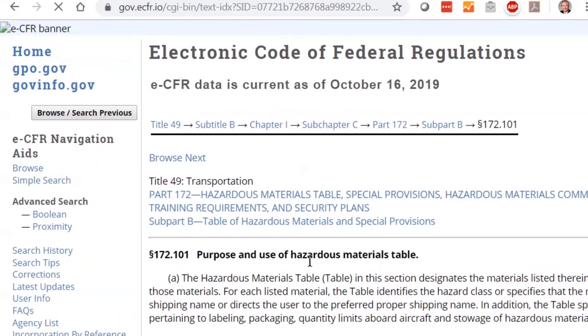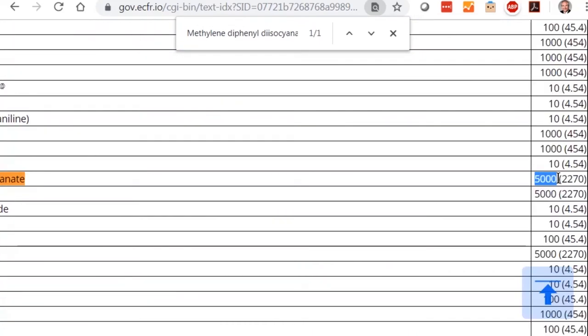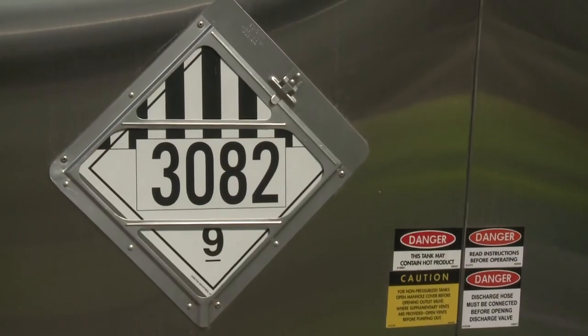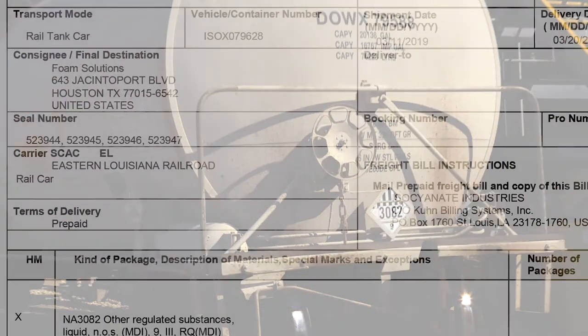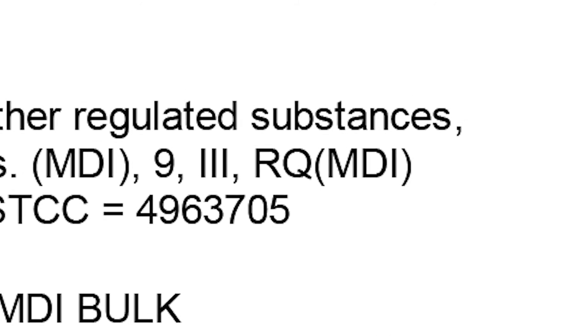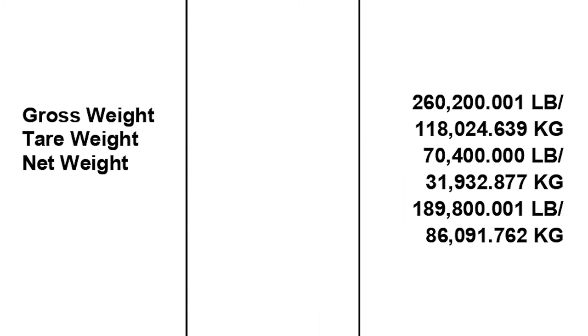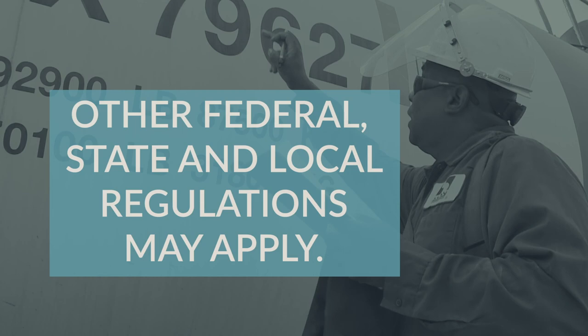In the U.S., the Department of Transportation (DOT) regulates the transportation of 4,4'-methylenediphenyl diisocyanate as a hazardous substance in single packages in quantities greater than 5,000 pounds. When in this quantity, MDI is typically classified as NA-3082, Other Regulated Substances, Liquid-NOS, Class 9, Packing Group 3. The letters RQ are normally entered before or after the description of the shipment when individual packages contain more than the reportable quantity of MDI. The storage and handling of MDI at your facility may be subject to other regulations, so modifications may be required.